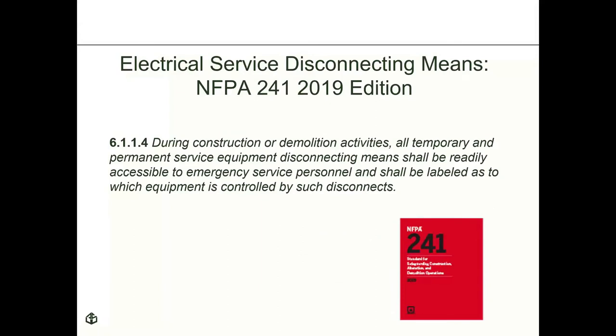Now the next change is the electrical service disconnecting means, which I think is a really good firefighter safety provision. This means you have to have one way to shut off all the electricity on a job site. That way the fire service, if they have to go fight a fire, knows everything is shut down, so it's safe to throw water and no firefighter is going to get electrocuted. It's just like the provision in permanent buildings, where there's one shutoff in all commercial buildings and one shutoff in all residential buildings, so they can ensure firefighter safety.